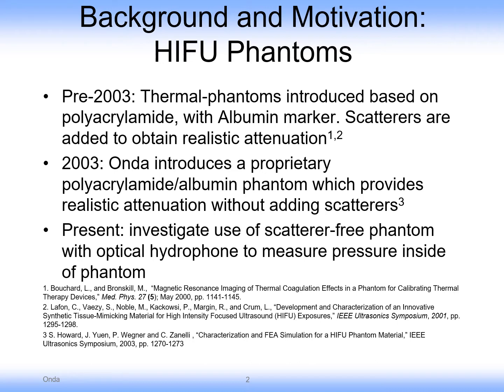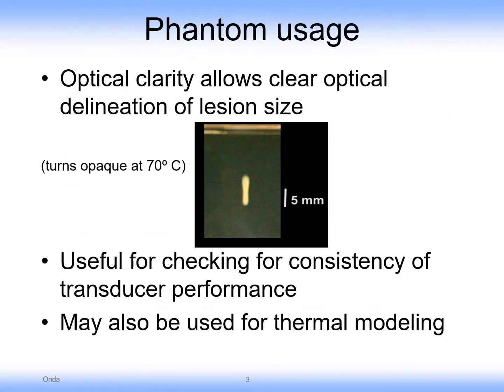Presently, we're investigating the use of this phantom with an optical hydrophone so that pressure can be measured inside of the phantom. Here's an example of the original optical use of the phantom. It turns opaque at approximately 70 degrees Celsius. This makes it useful for checking the consistency of transducer performance, as well as for thermal modeling of HIFU dosage.